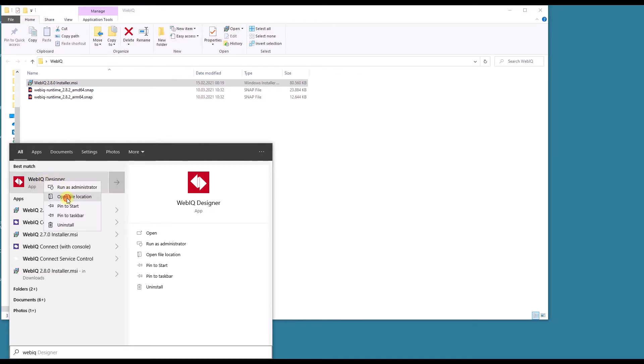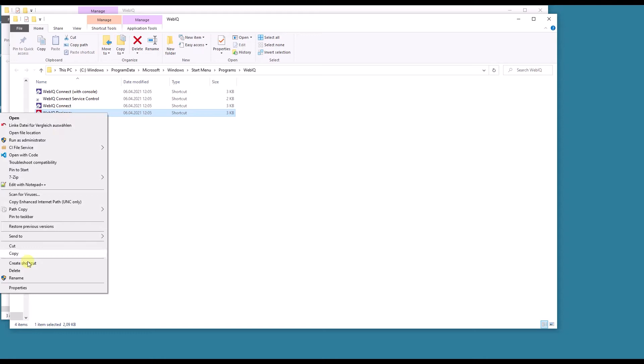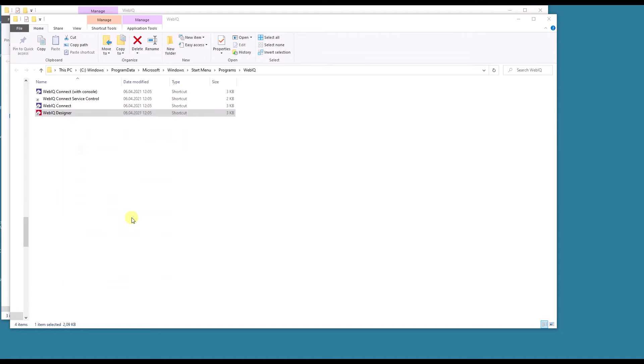So we do that here. We have the shortcut called Designer, and by modifying the properties — the target — it's required to provide additional information about the ctrlX and the WebIQ port. We have two parameters: one is the host, which is local host in my case, and we have the port under which the app installed on the ctrlX will be available — this is 10123 by default. Now that we have done that, we are ready to create our first HMI project.